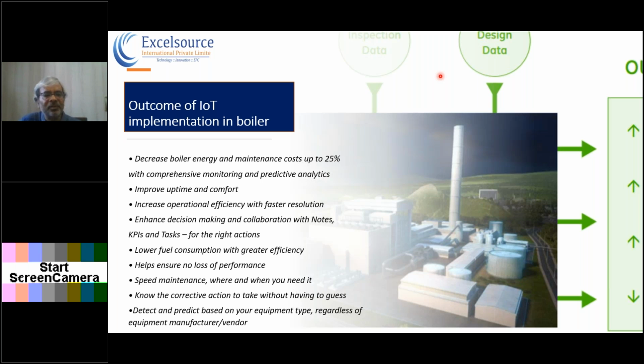So, improved uptime and comfort, and increased operational efficiency with faster resolutions. Any problem such as imbalance of the ID fan can be immediately identified, and prior to breakdown, we can resolve it. As an example, decision making can be very fast and effective, without even having somebody on duty in the night shift. We can check the data on record from the IoT and then take decisions. This will definitely improve the efficiency, so we have less fuel consumption. It will expedite the maintenance as and where it is needed. The corrective actions and the fishbone analysis, normally done by the team, can be very fast, and we can probably never repeat those failures in the future.